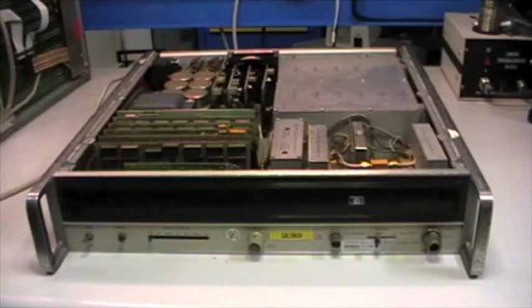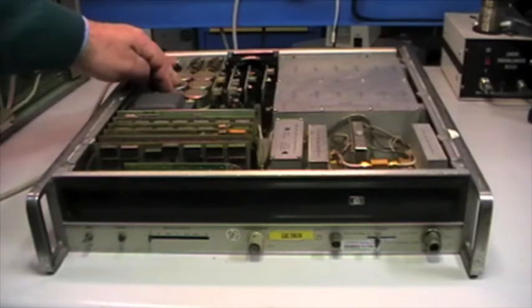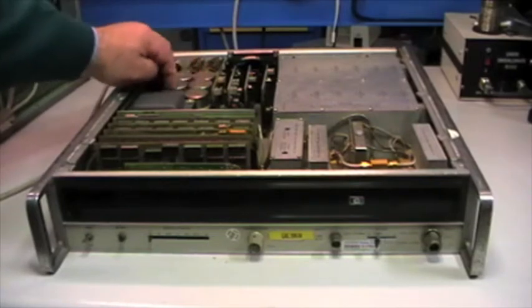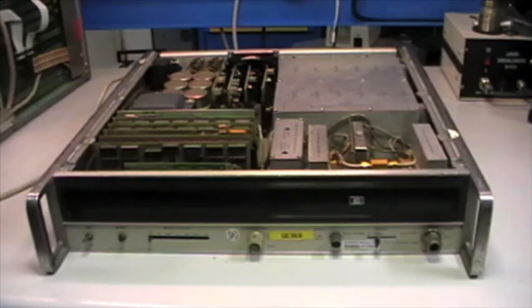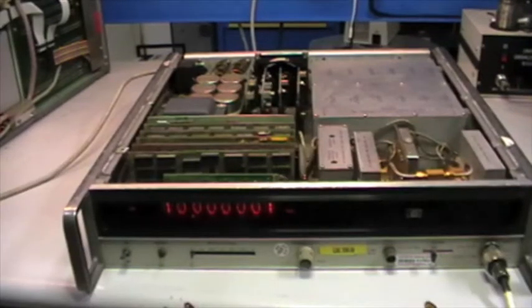So let it sit at this voltage for a few seconds in order to let the huge amount of capacitors here reform themselves. So rising up. Okay, I start to see, I'm not sure that you can see on camera, the Nixie starting to glow. Okay, the fan starts spinning. Let's set it to this lower voltage for a few seconds. I will leave the instrument for a few minutes at this voltage, and then I will be back. So the unit has been running for almost 10 minutes at 160 volts AC.